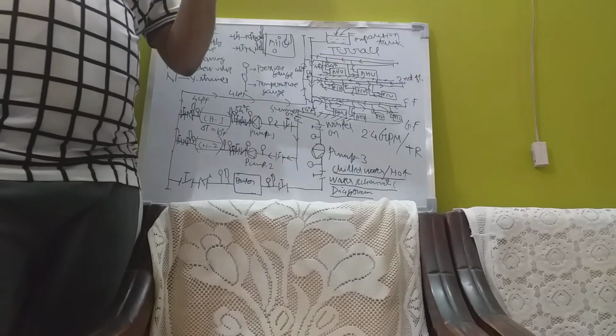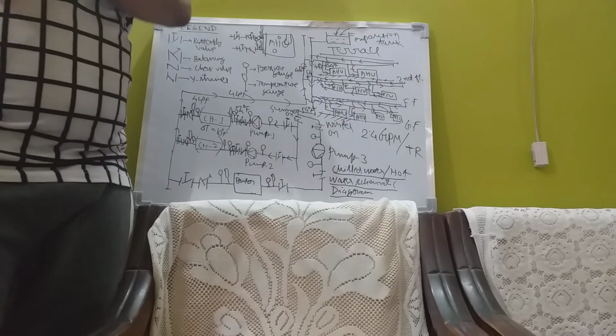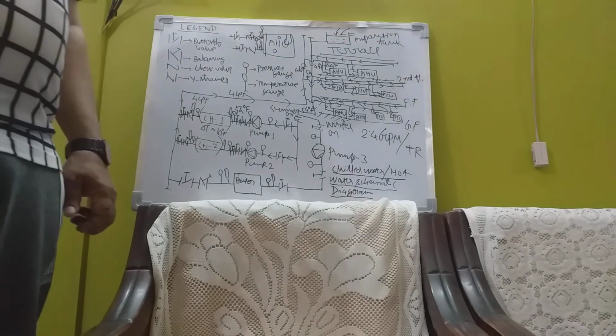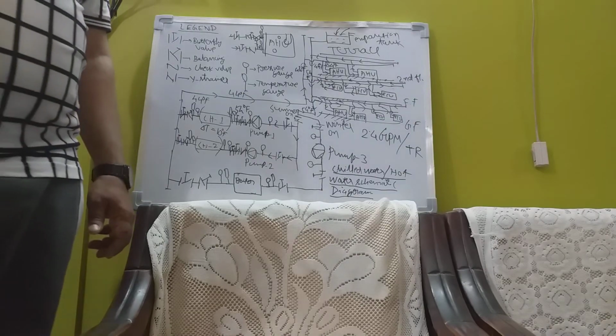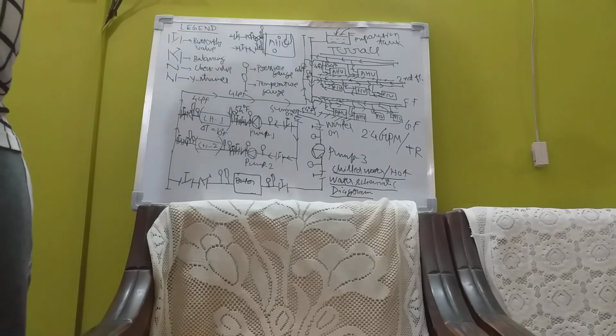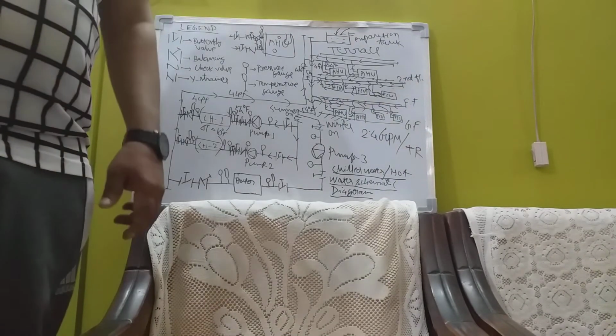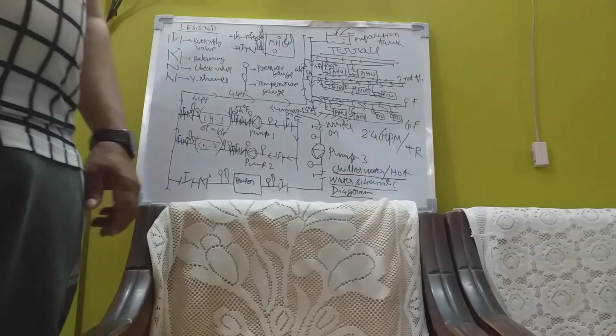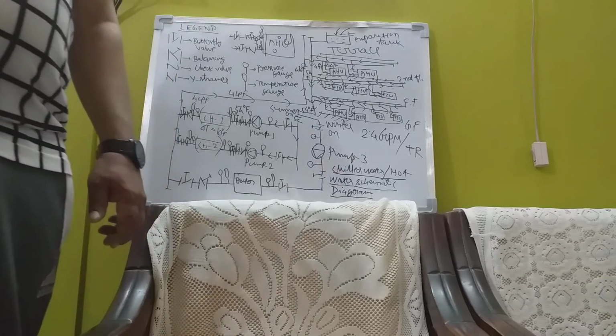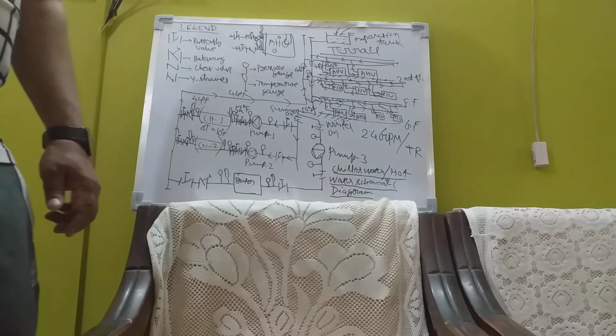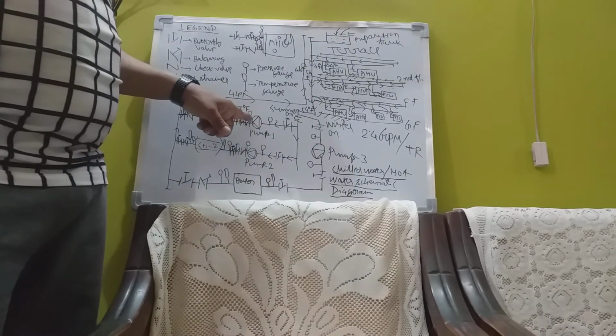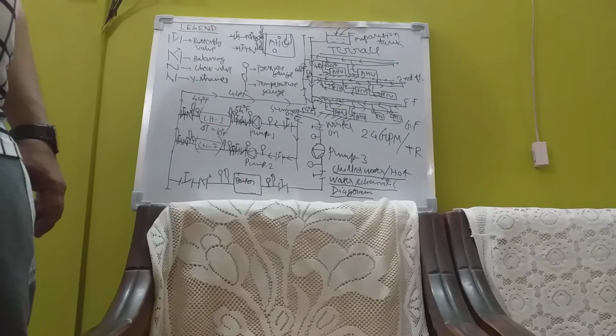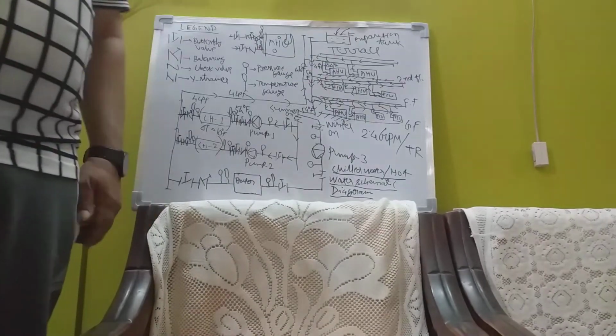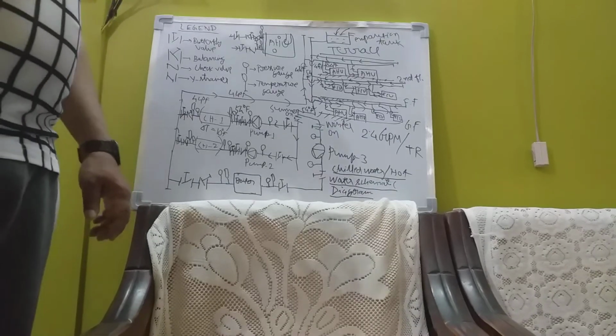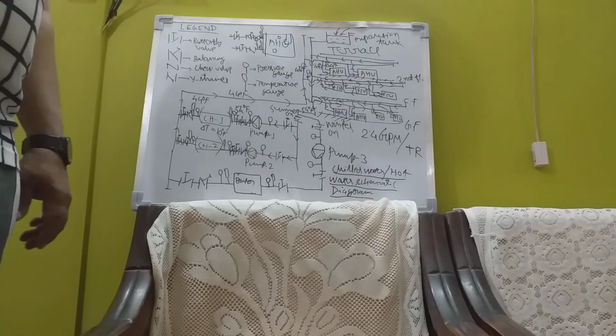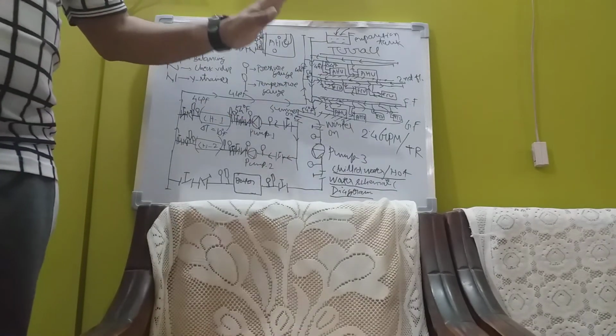Now how does it modulate? In summer, the room load at 6 p.m. in the evening is much less at 12 in the night. So the compressor modulates its speed accordingly and the power consumption decreases. So while you are paying 2000 to 2500 in the case of general air conditioners, you are paying only 1000, half of that, in the case of inverter air conditioners. The same principle is being used here in the chilled water pump system or hot water pump system. We modulate the pump speed along with the temperature and control it accordingly. These are all about your chilled water and hot water pumps. I think the whole picture is clear to you and you are able to understand.